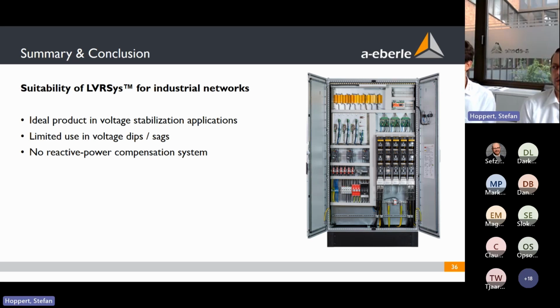So I do the example with the 20% system. So if the voltage dip is 40%, that means the rest of the voltage is 60%. And if the rest of the voltage is 60% and we raise the 60% rest voltage by 20%, then it means we reach 72%, not more. And then the voltage goes back whenever it comes back. So it means it's not ours, so we cannot help to bring it back to the nominal point. So then the voltage dip has to come to an end.